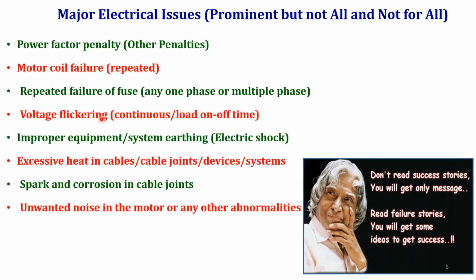Then repeated fuse failure. Again, it is one particular phase where the fuse failure is predominant, or sometimes multiple phases also. Then we have voltage flickering. This is a common issue whenever you have electrical drives or electronic control equipment connected to a main power line, automatically the voltage flickering will always be available. Keep in mind that it is sometimes continuous, or sometimes when a heavy load is turned on and off, the voltage flickering is available. Then improper equipment and system earthing may lead to leakage current and similarly electrical shock.